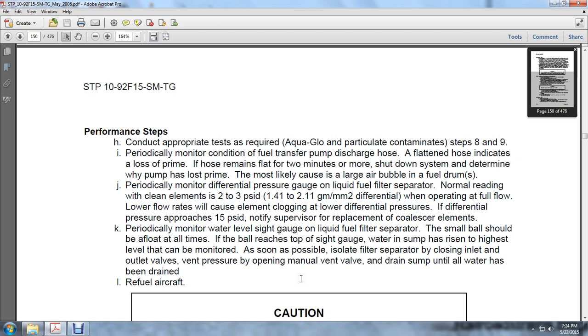Periodically monitor the differential pressure gauge on the liquid fuel filter separator. Normal reading with clean elements is 2 to 3 PSID when operating at full flow. Lower flow rates will cause element clogging at a lower differential pressure. If the differential pressure approaches 15 PSID, notify the supervisor for replacement of the filter elements.